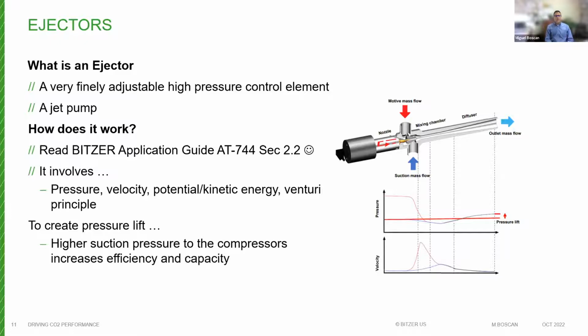BITZER has an excellent guide, AT744, and the principle of how it works is described much more elegantly in section 2.2. So I would suggest anybody interested go to that document for more details. Since this pressure lift is done without having to add electrical power to the system, the increased pressure lift has a direct and positive impact on system efficiency, which is what we're all trying to achieve. In our going forward with our rack systems, CO2 has some unique characteristics that we can take advantage of to do this well.